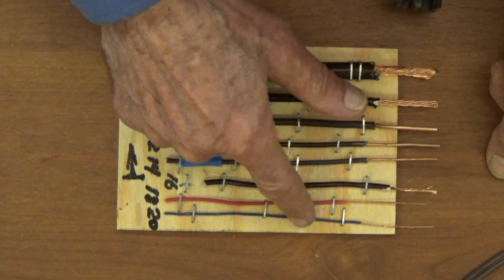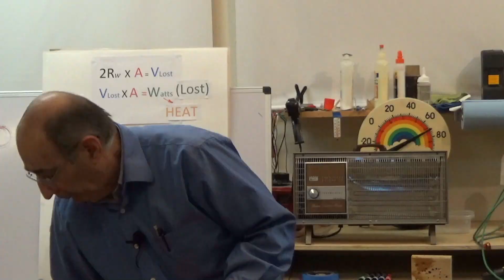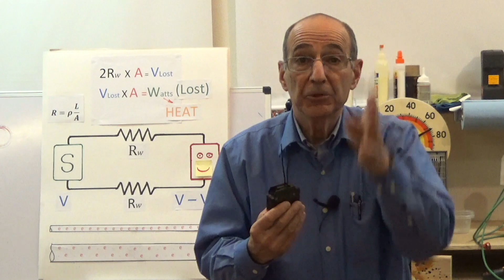Now, because of these different thicknesses, they have different amperage capacities. So, like we were talking before, the wires that come off of here need to be able to handle the rating of the circuit breaker. This is a 20 amp circuit breaker - this wire needs to be able to handle 20 amps in the situations you find them in a building. It's not out in open air, so it's often in a space where it doesn't dissipate heat rapidly. So they have a certain rating by code, and this is a number 12 wire, which typically goes with a 20 amp circuit.